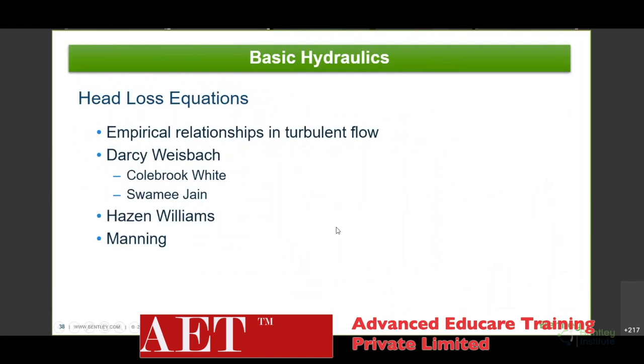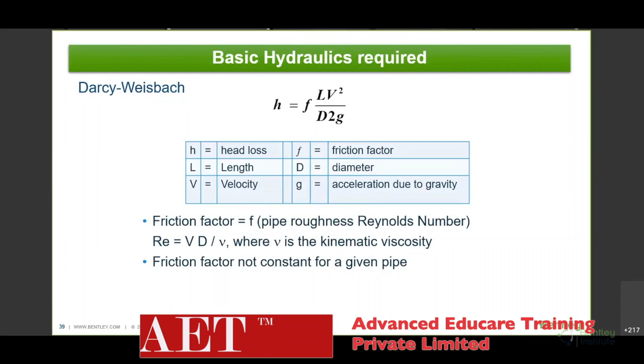Now let us take a look at a few head loss equations, which we have studied in theory. The most commonly used equation is the Darcy-Weisbach equation, that is nothing but H is equal to FLV squared upon 2GD. Here in this equation we have to find this F value, that is the friction factor value, with the help of this very tedious Moody's diagram. To determine F, we need the Reynolds number and the relative roughness. Here on the x-axis we can see the Reynolds number, and on the y-axis the relative roughness. This is an iterative process and it must be done to determine the F values for the Darcy-Weisbach formula.